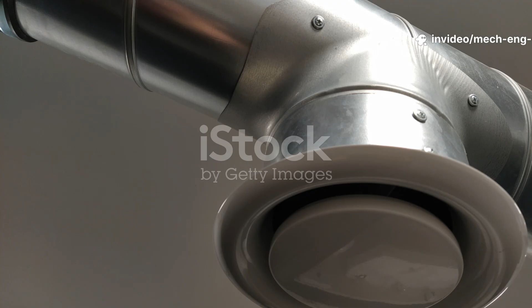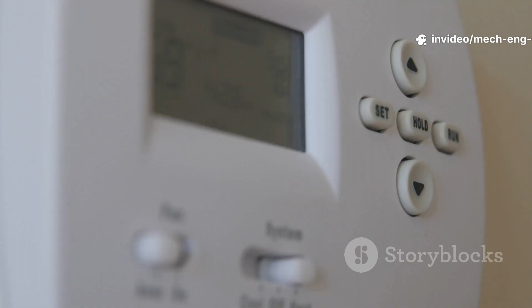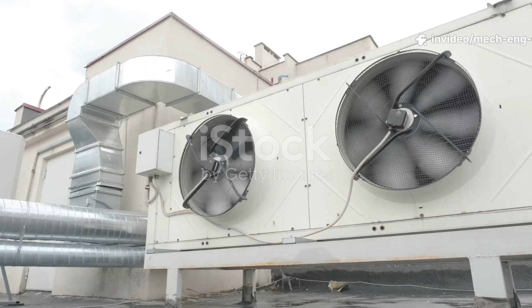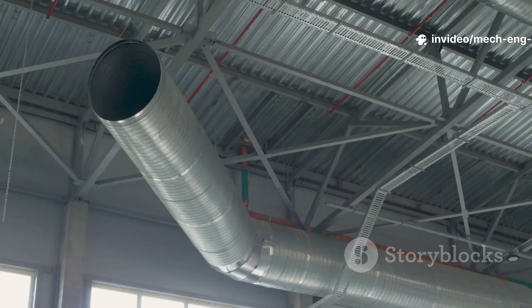1. What is a VAV system? A variable air volume, VAV, system controls the amount of air supplied to each zone, instead of keeping the airflow constant like traditional systems. In simple terms, it changes airflow, not temperature, to meet the cooling or heating demand of each zone. This makes it smarter, more comfortable, and energy efficient.